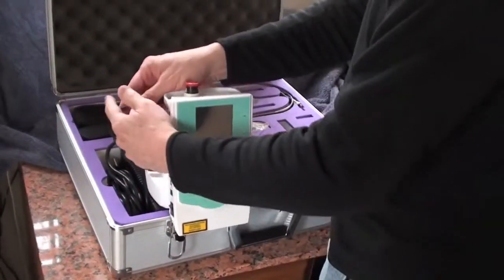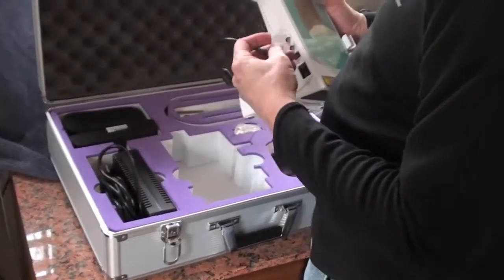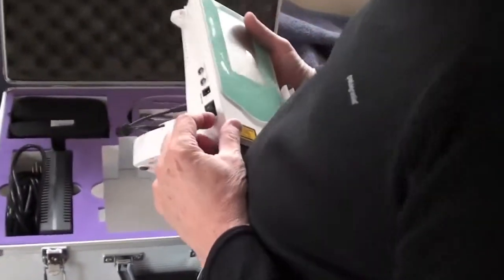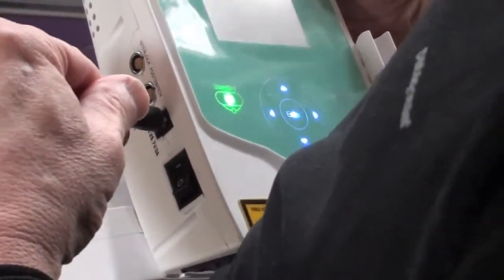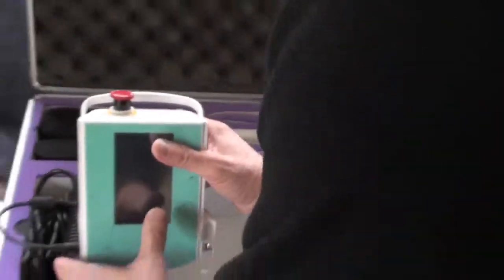We'll show you how to first hook it up with the battery. I wouldn't recommend hooking this up until you make sure it's off. This is in the off position. Everything should be in the off position or it will spark. That's the off position. Okay, hook it up like that.